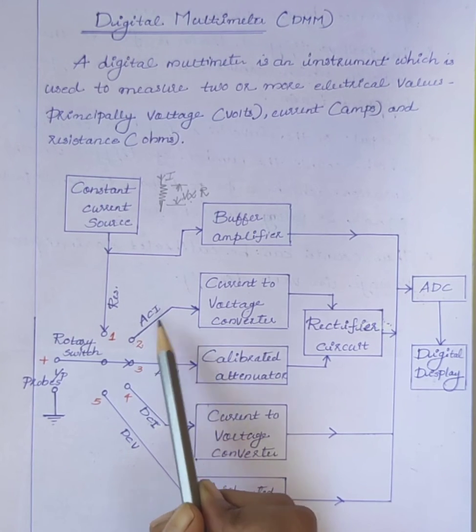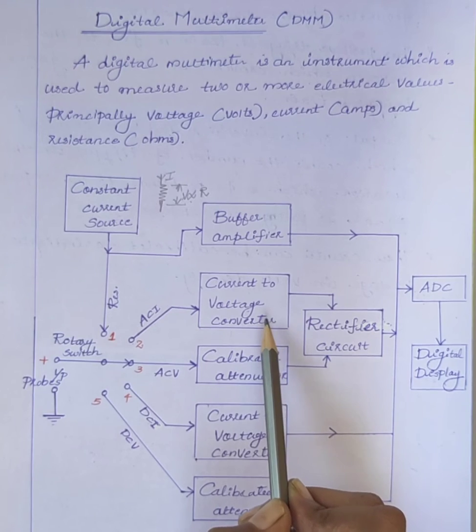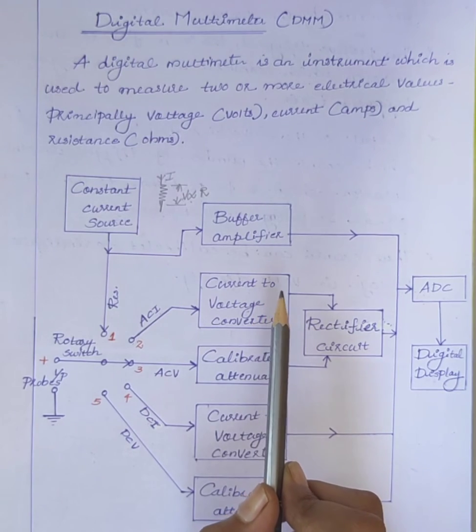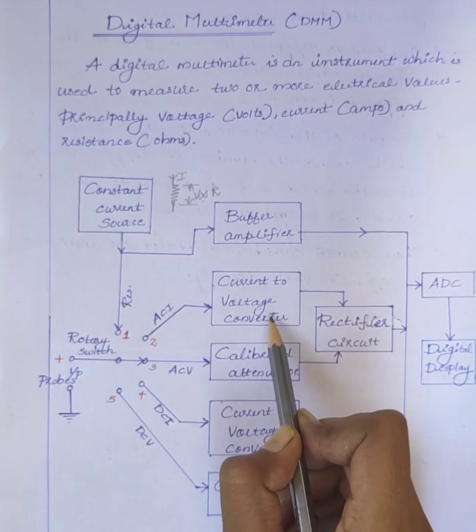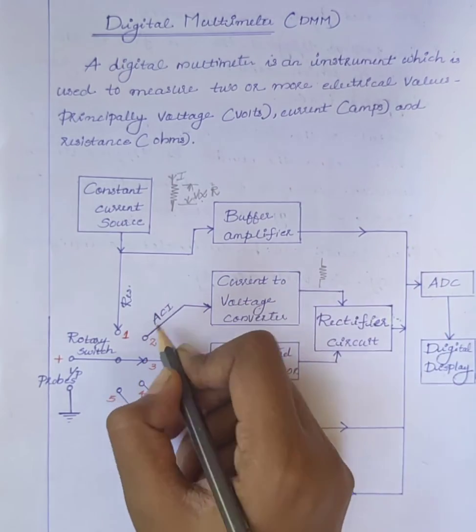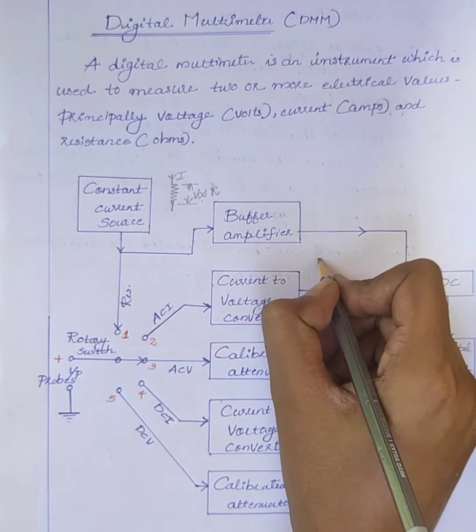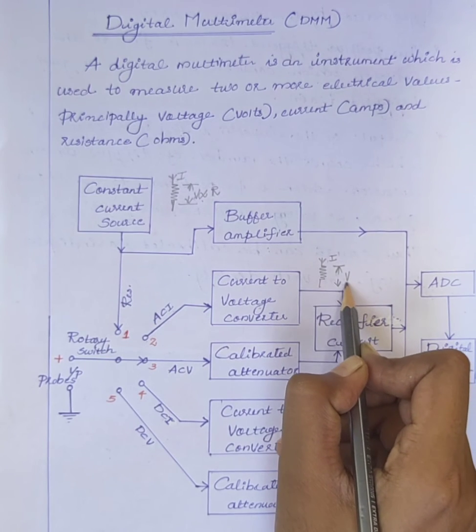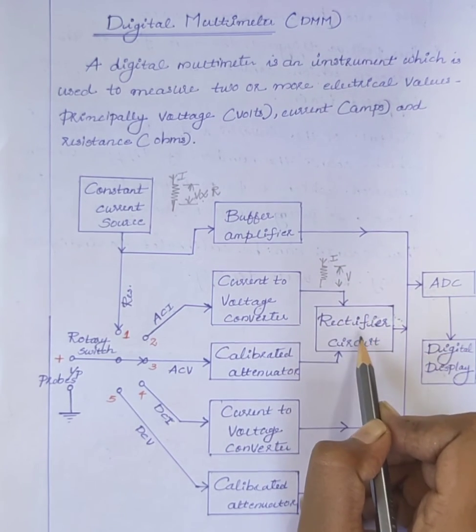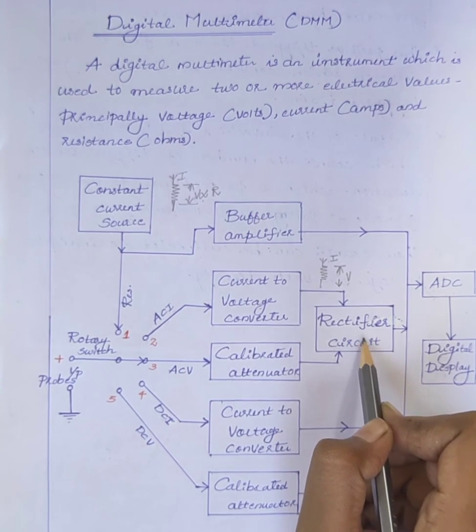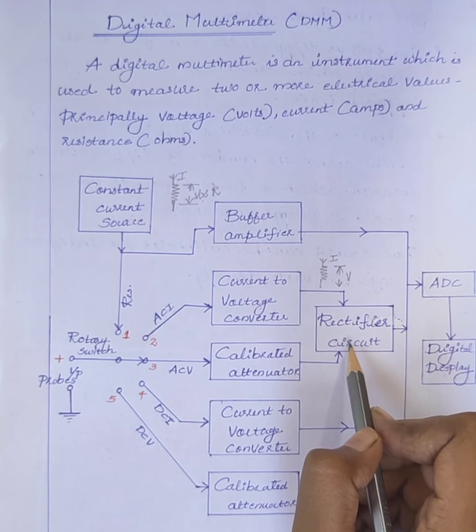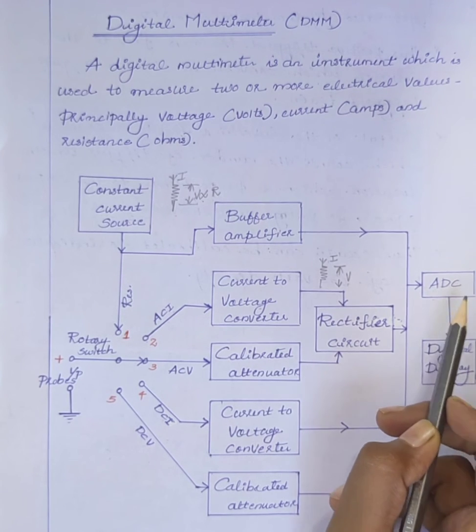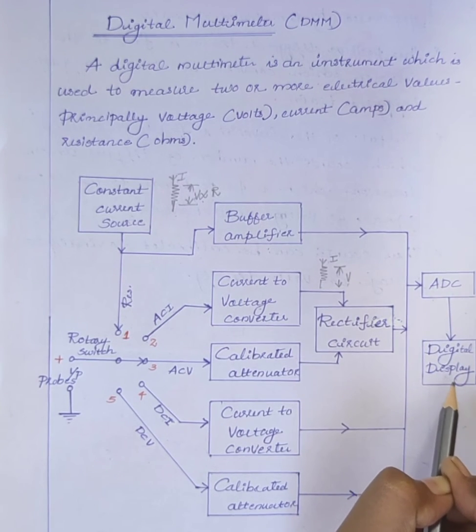Initially, the AC current is given to a current to voltage converter. A current to voltage converter consists of a resistor. The unknown AC current is passed through the resistor, and a voltage which is proportional to this current is obtained. This AC voltage is given to the rectifier circuit. The rectifier circuit converts AC quantities into DC and gives them to the analog to digital converter, and the value is displayed on the digital display.